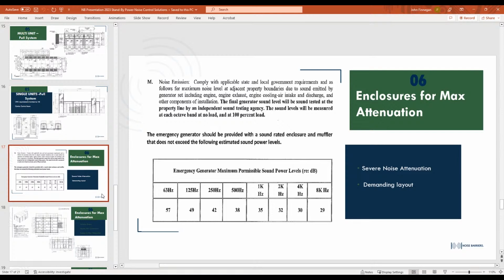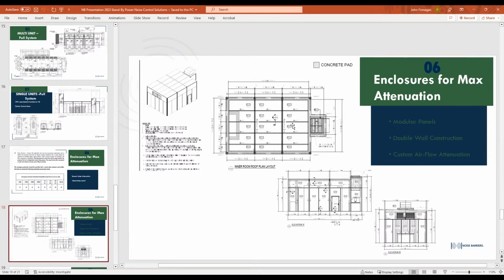I need 50 dBA. And then you see here's a specification where it says the permissible sound power levels. This is a big lift - this was a special max application, I would say. Again, it's severe attenuation, demanding layouts, put right next door to an office building, right next door to apartment windows. It's got to be silent. So in that case, everything is going inside the enclosure.